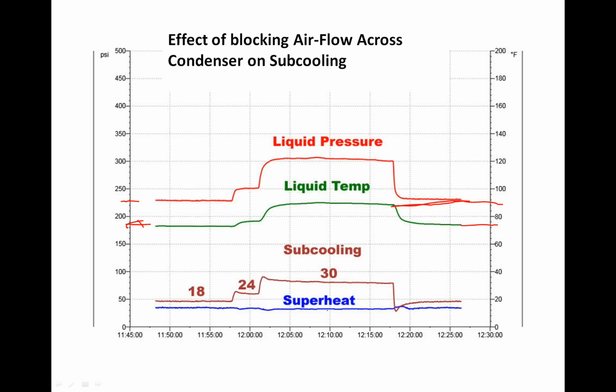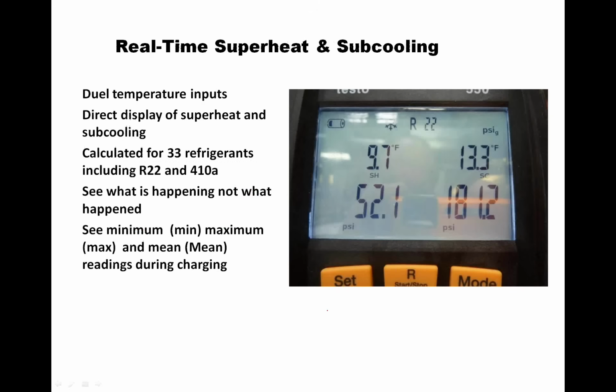The reason I tell you this is some guys will tell you on a mild day, go out and wrap cardboard around the condensing unit and just raise it up and try and charge it by subcooling. Well, if you do that, you're going to undercharge the unit because you're going to indicate higher subcooling than you actually have. You're going to come back, you're going to think you got a leak because you go, oh, I charged the thing to 10 degrees of subcooling. When I came back, now it's only 2 degrees of subcooling. Well, it's because you've changed the design characteristics of the condenser. Can't do that. All right.